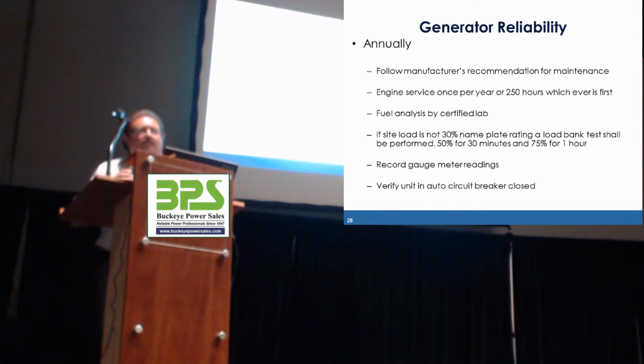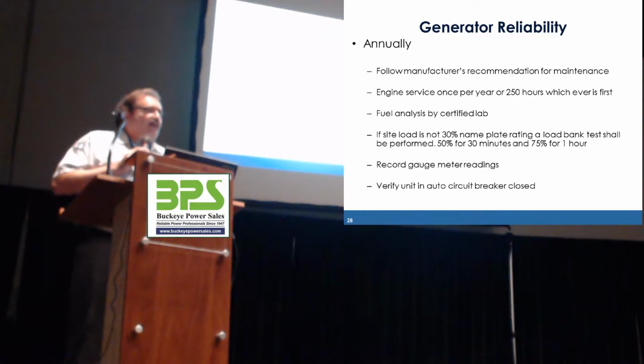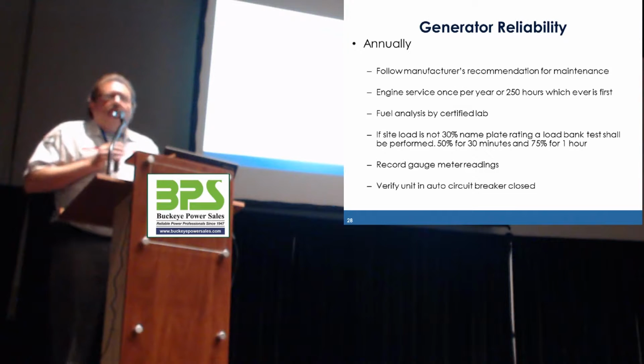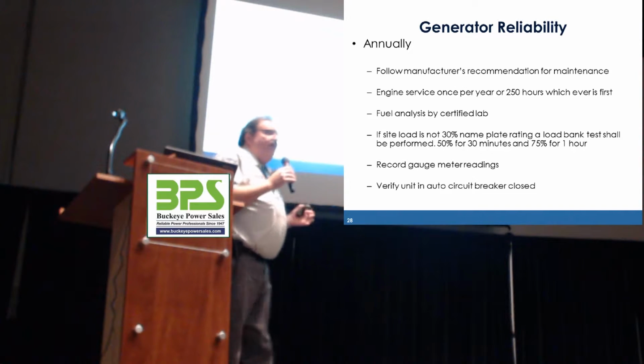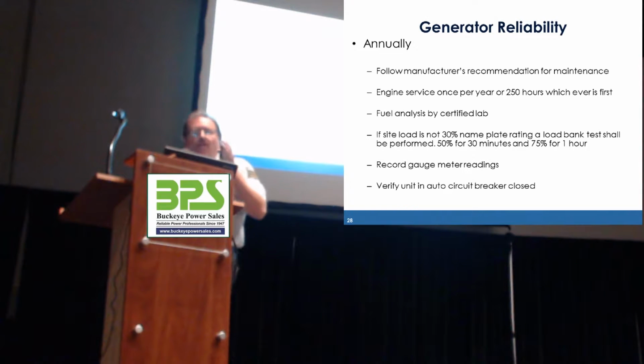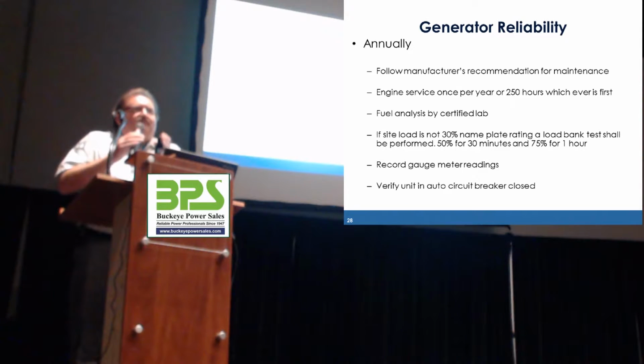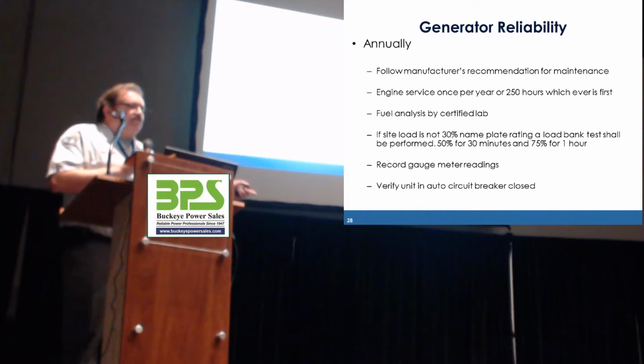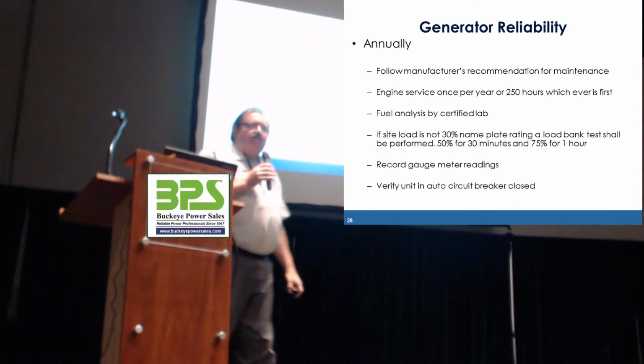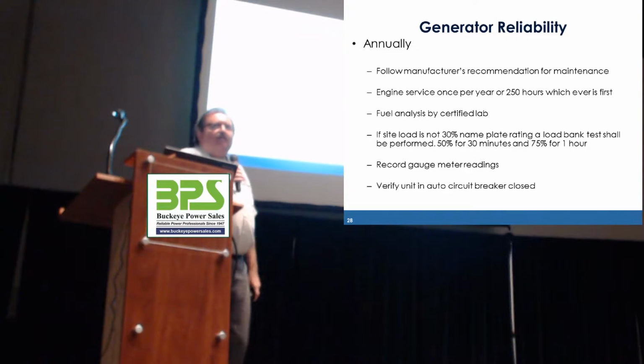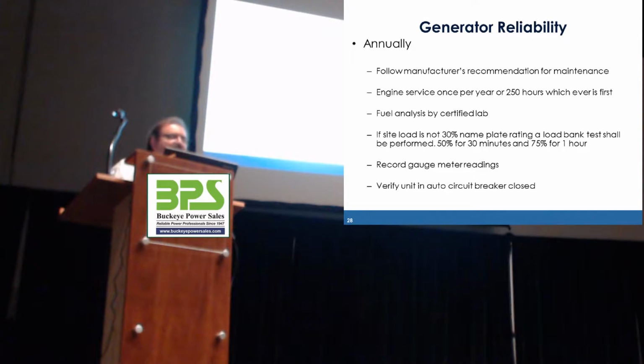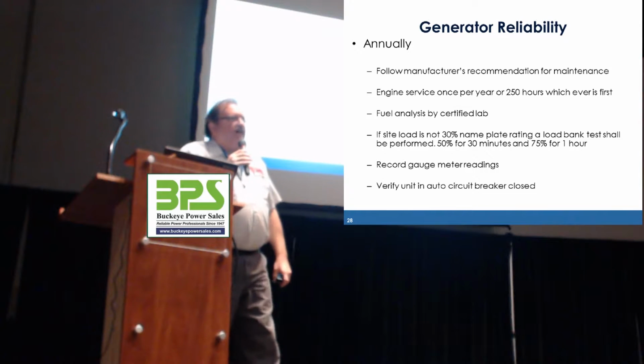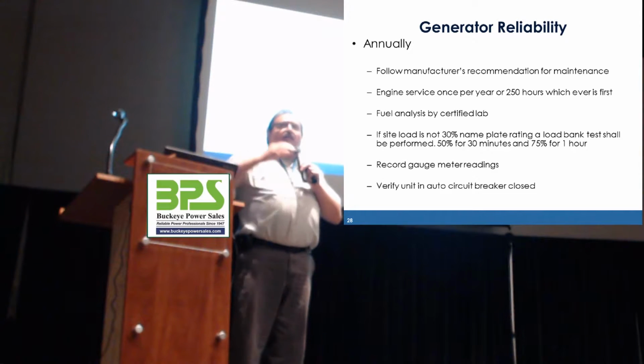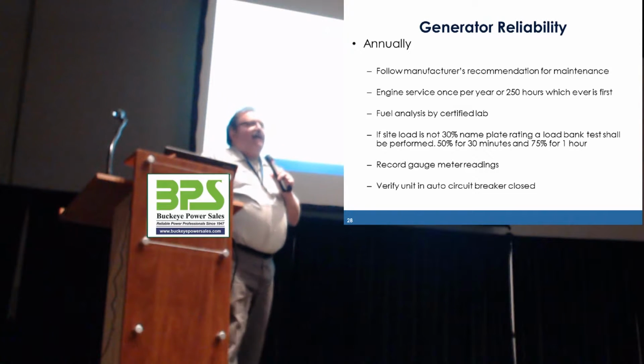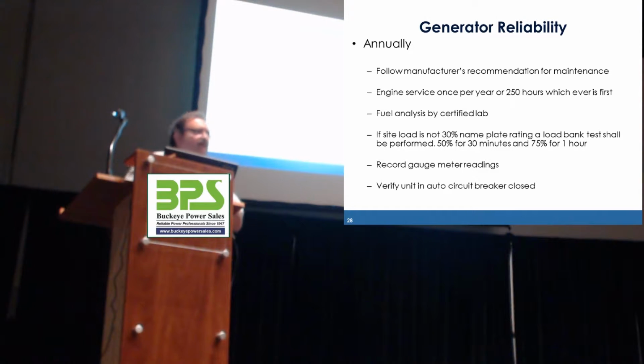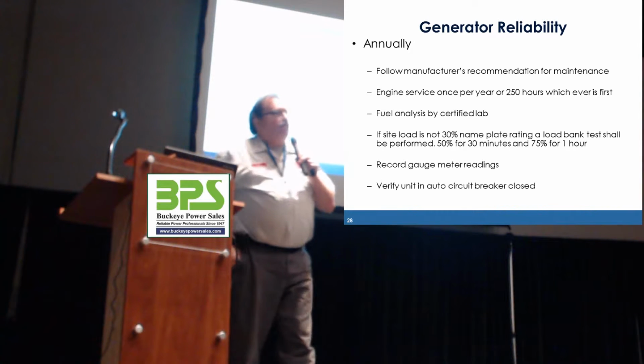Even if you have that 30%, load bank testing annually is a good idea, because any weakness in a machine is going to become evident under that test. Just like when he was talking about, you don't know what that bus bar is going to do until you put that full load on it. You don't know how it's going to react. That generator could be perfectly fine running at 35% load. But let's just say you add load onto it, and now it's at 60% load, and it's never run at that. There's no guarantee that that machine is going to work.